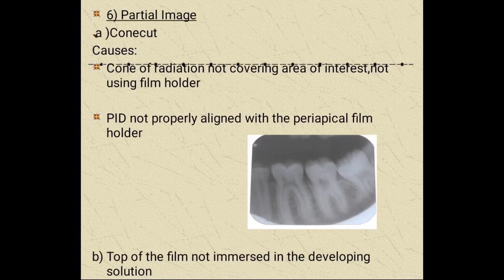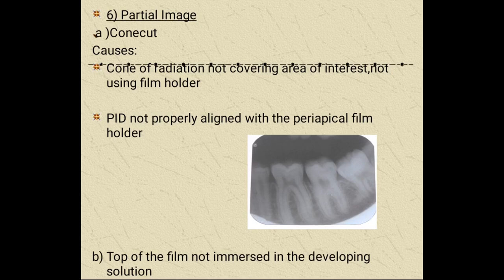A partial image, also known as cone cut, occurs when part of the image is missing because the exposure does not happen properly — the cone of radiation is not covering the area of interest, no film holder is used, or it is not properly aligned with the periapical film holder. Also, the top of the film may not be immersed in the developing solution. We can correct it by making sure the cone is properly centered over the area of interest both vertically and horizontally, ensuring the PID and aiming ring are aligned, maintaining the level of solution in processing tanks, and making sure the film is completely immersed during processing.